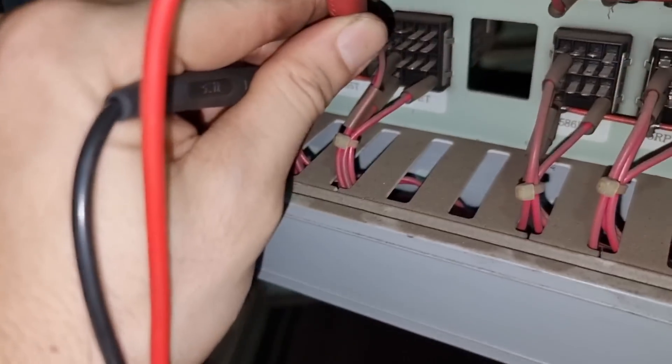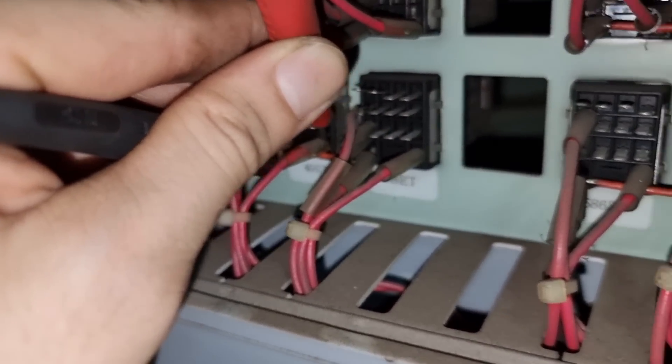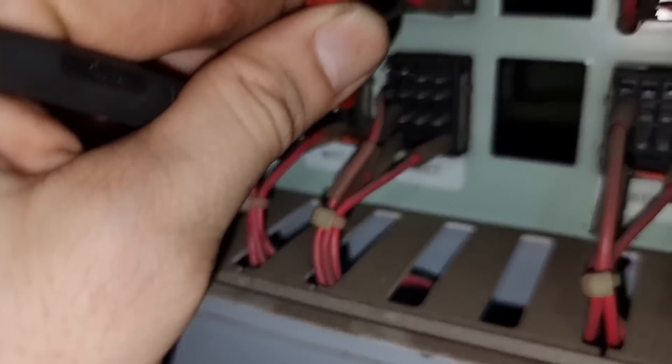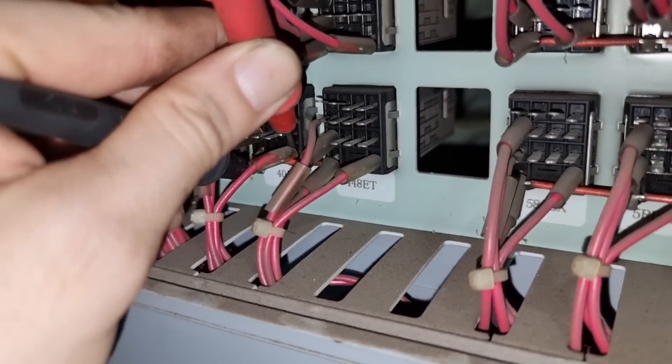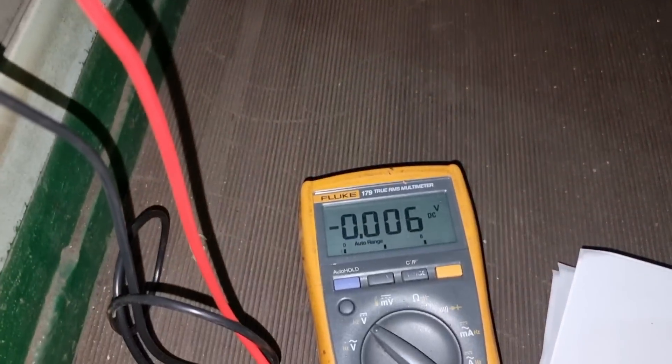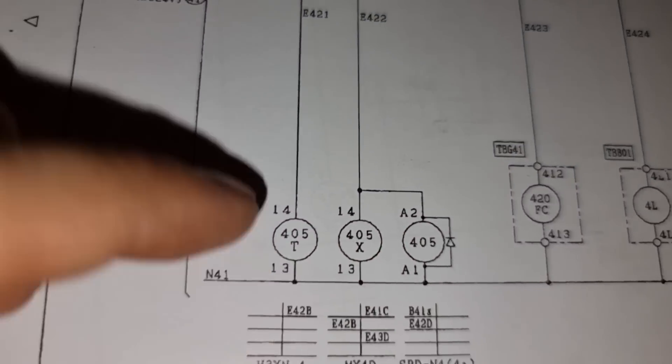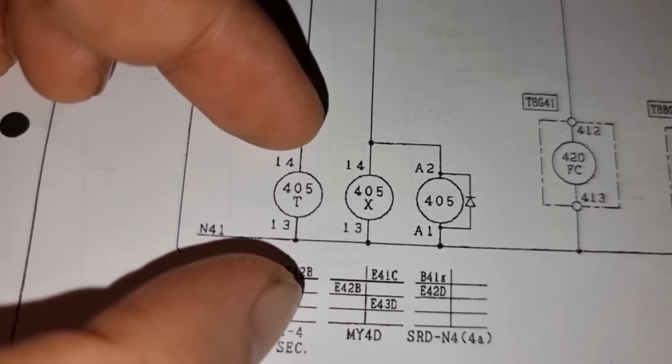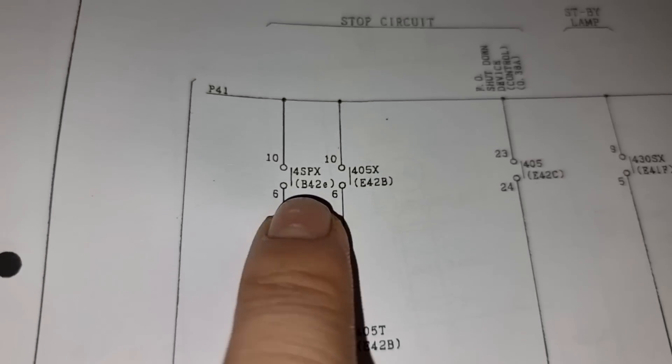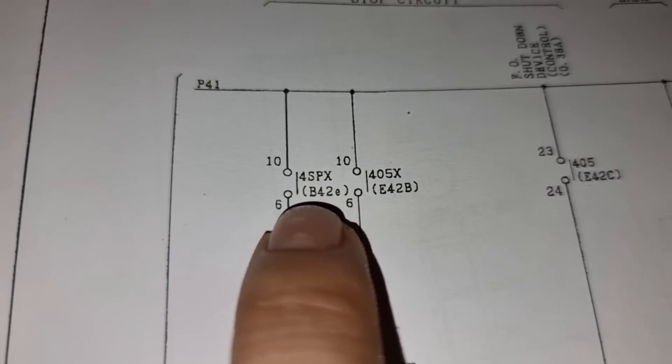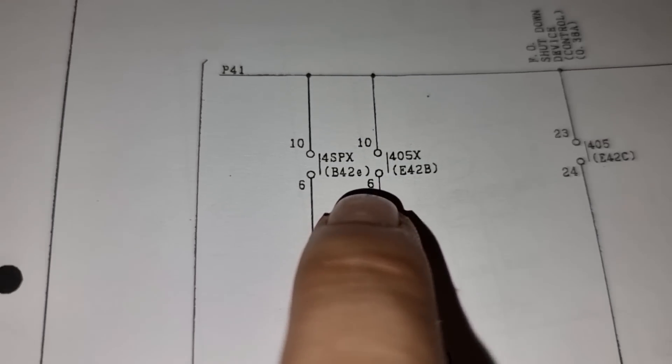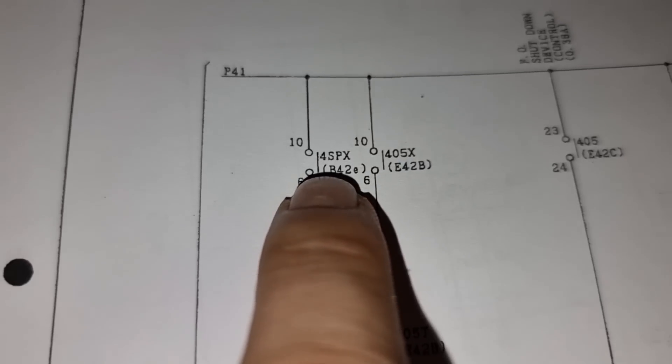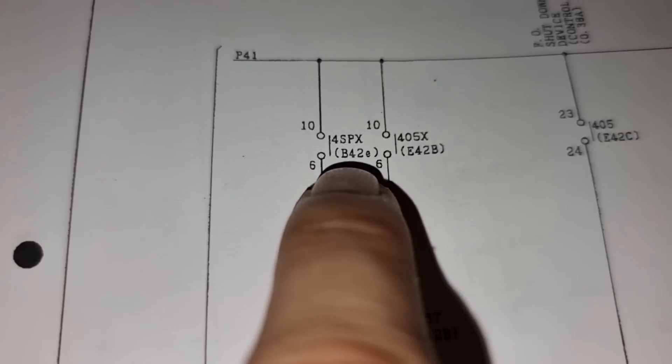And then I again ask the engineers to activate the stop command and measure the voltage of this timer, which is not getting 24 volts. Now we are also sure that we do not have voltage on 13 and 14. And the control contacts for that one is this 4SPX, which we need to check the relay for SPX.